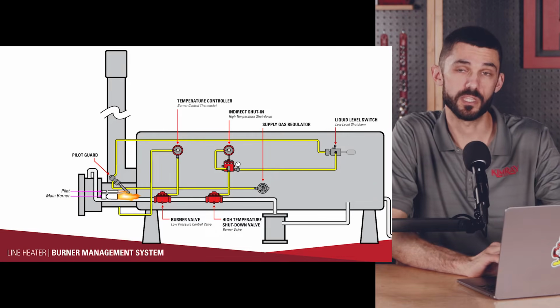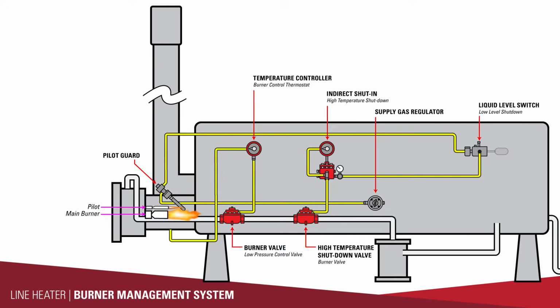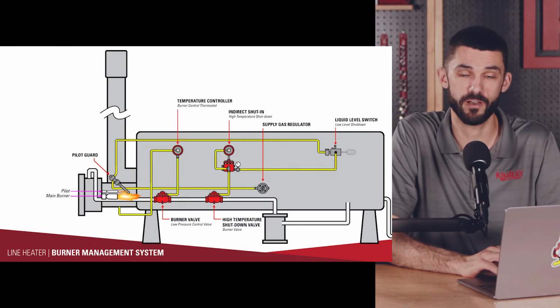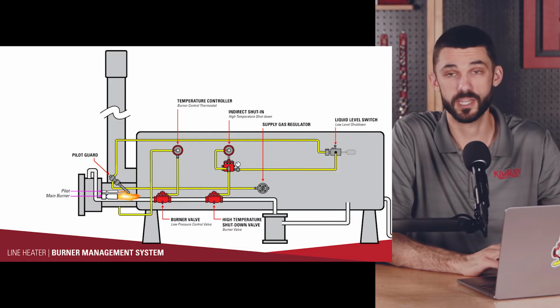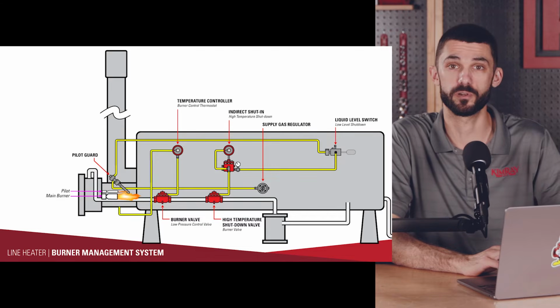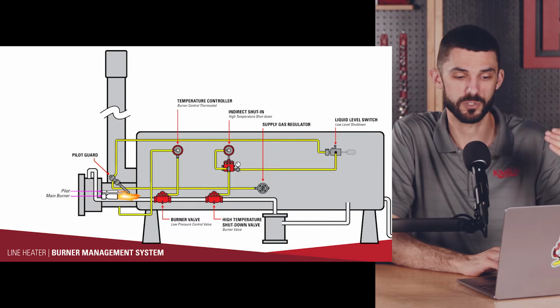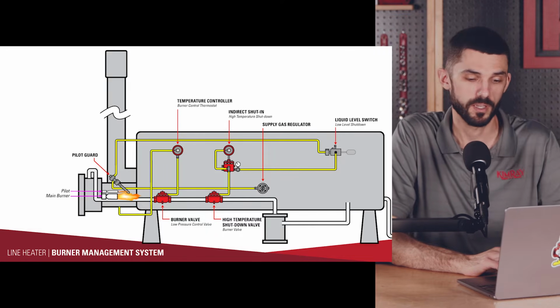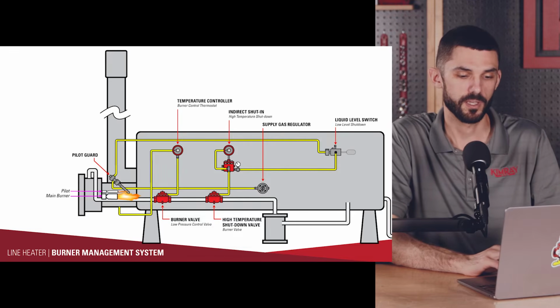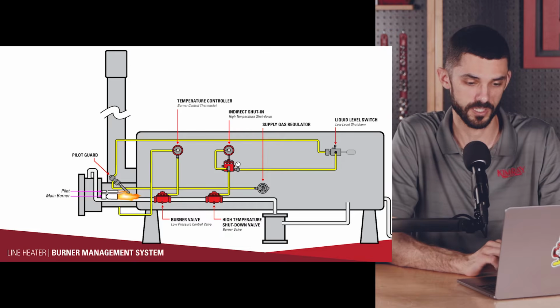So we have two burner valves in this example. We have one that's the normally operating burner valve. So the T12 will be communicating with that, opening and closing it to control the temperature inside of the vessel. Then we also have a secondary safety shutdown valve that will be communicating with the high temperature shutdown valve. So if we ever get above our high temperature set point, most likely that's an indication that our burner valve has failed in some way. It's staying open when it shouldn't, and so it's continuing to feed the burner with fuel, increasing that temperature up to that high temperature set point. And so we have a secondary valve that will shut down. It's downstream of the burner valve, as you can see in this example.